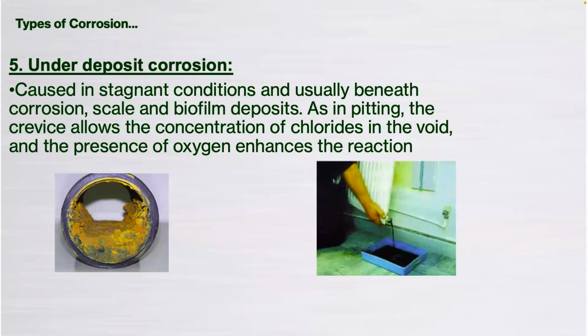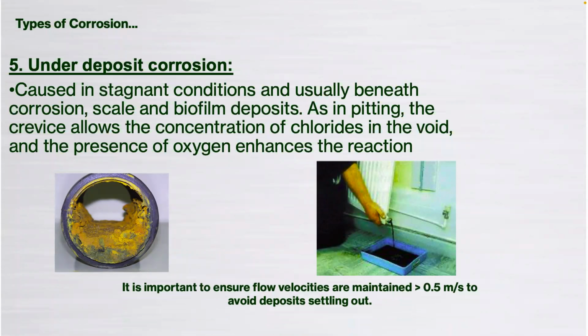And you'll see here as well that, you know, radiators is a very, very common form of under deposit corrosion, as one would expect. We may see that on pipework as well. If you've got lateral runs of pipework, or you know, horizontal runs, you might see pinholing as well from under deposit corrosion. But it's usually where higher volumes of deposits settle out, which is normally radiators, or it could be a vessel of some sort. So it's really important that we maintain the flow velocities correctly.